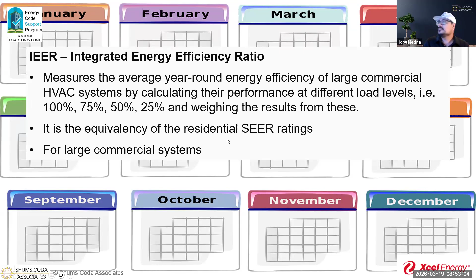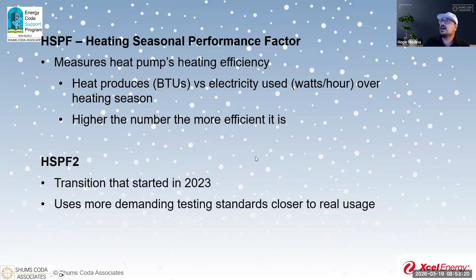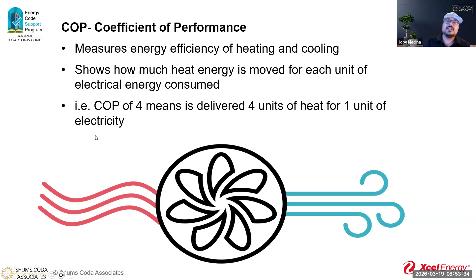HSPF, like we talked about, this is measuring the overall heating efficiency, but then the HSPF2 transition once again occurred in 2023, where they updated the federal standards and updated these to be more reflective of real usage, basically. Coefficient of performance. This is basically, once again, breaking this down. The COP of 4 means 4 delivered units of heat for 1 delivered unit of electricity. And remember, that's looking at a BTU to BTU ratio there.